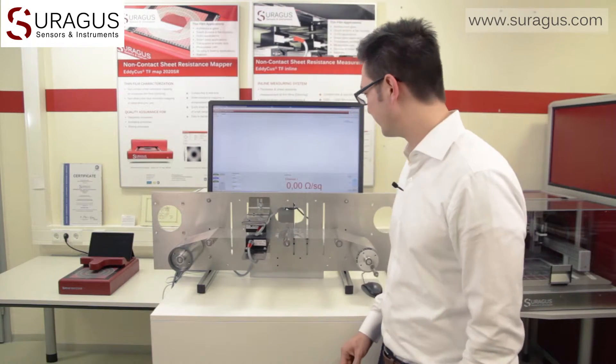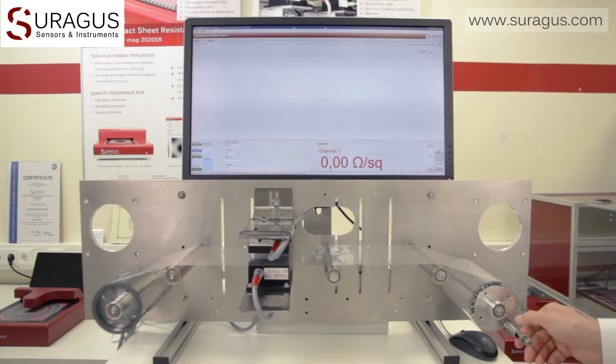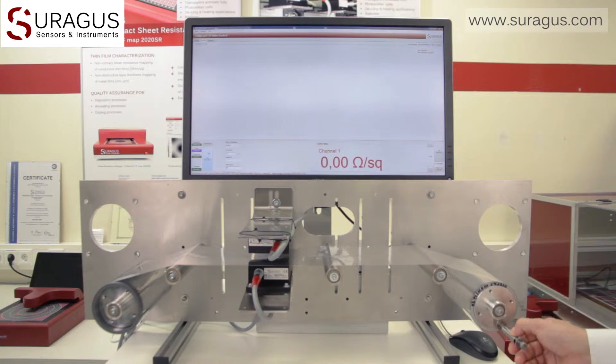Operation of the sensors is possible in direct communication with the coating machine or, as we do here, by using the Suragus inline software. To start the measurement, we just activate the sensors with the record button. As soon as the sensors approach a conductive coating, the precise sheet resistance measurement starts.